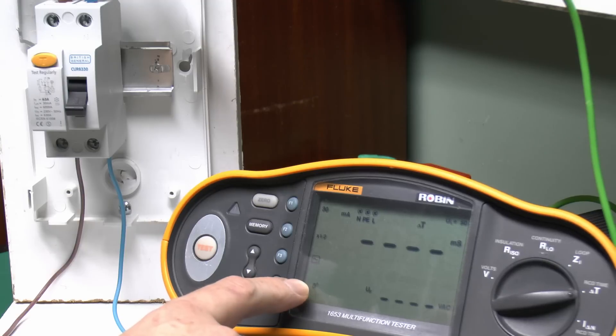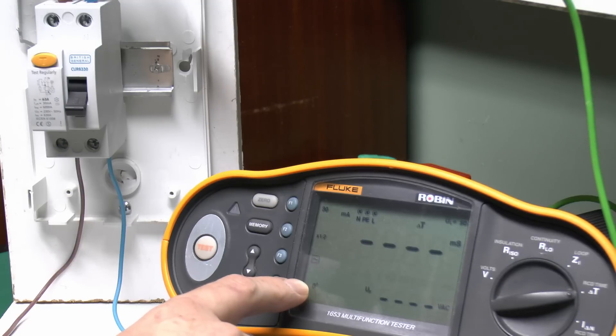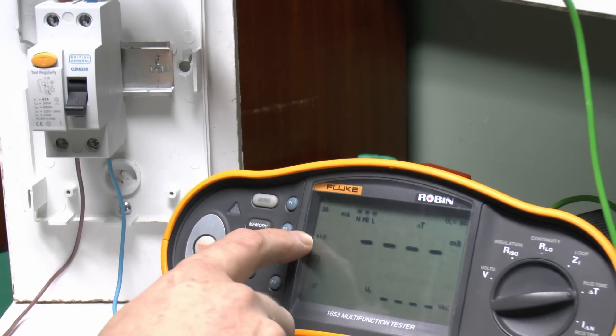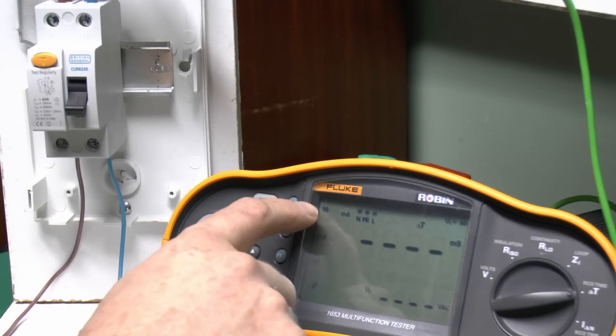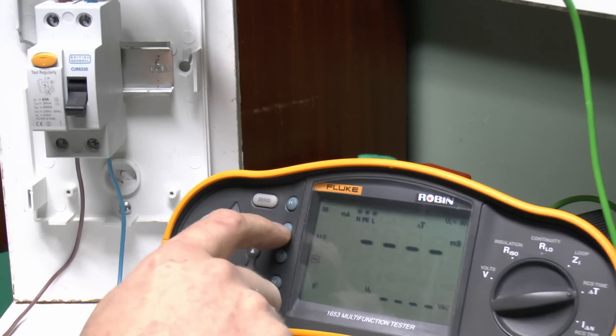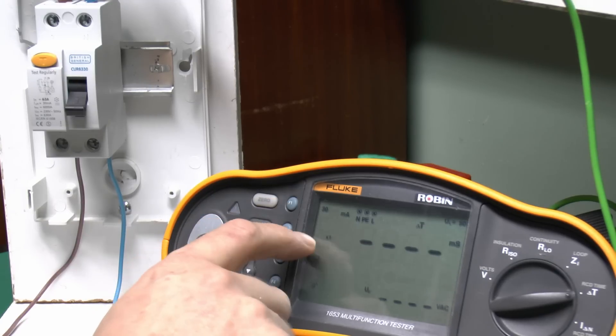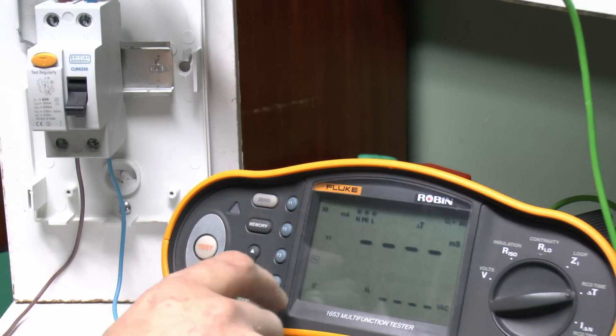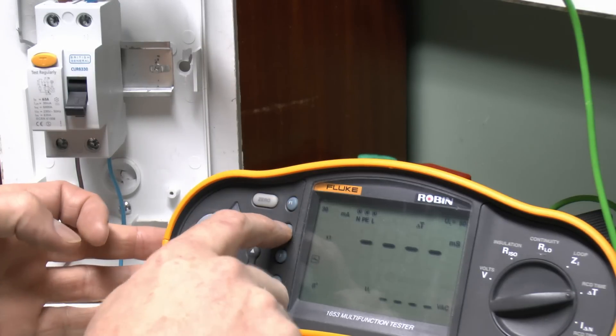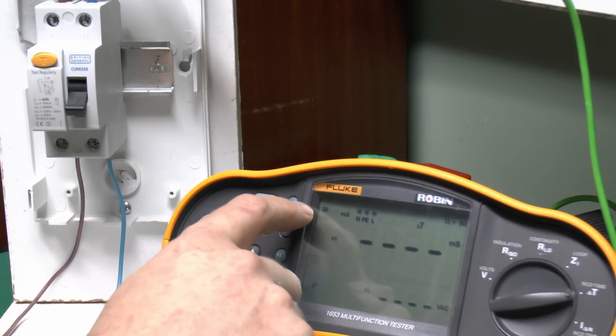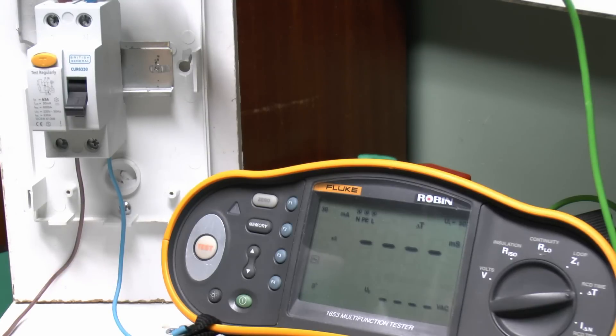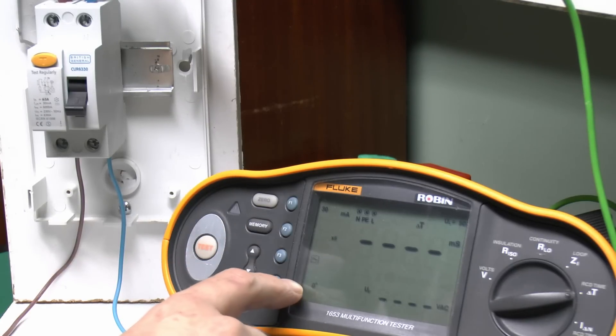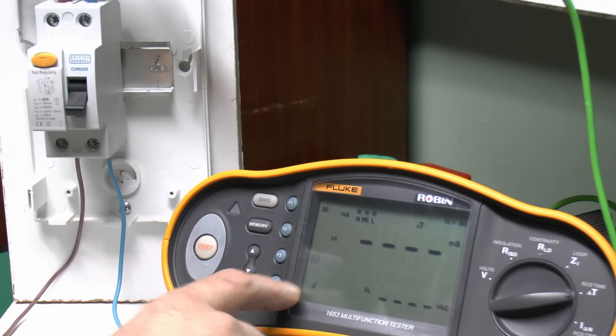And there's three currents which we'll be measuring at. The first one is a half, so in this case, that's half of 30, so 15 milliamps. And the next one would be one, so again, that's just the 30 milliamps there. And times five, which would be 150 milliamps for this particular device. And again, there's three of those, and you need to test them at both 0 and 180. So that would be a total of six separate tests.